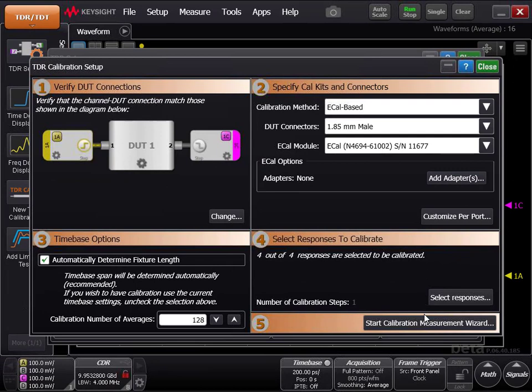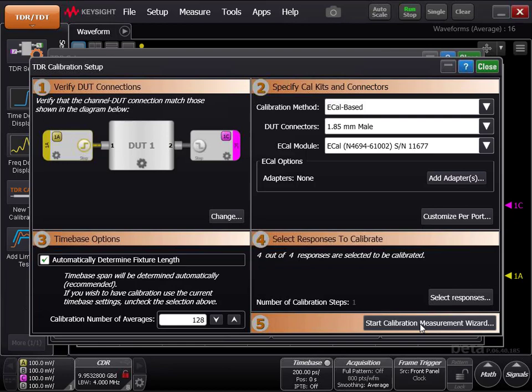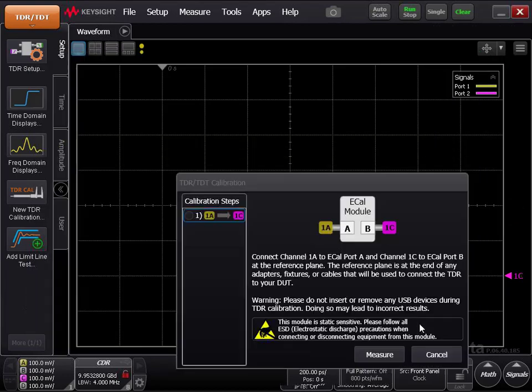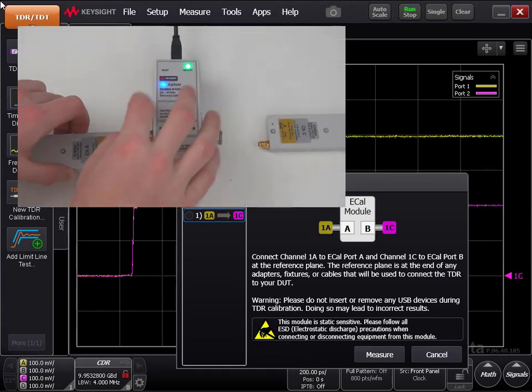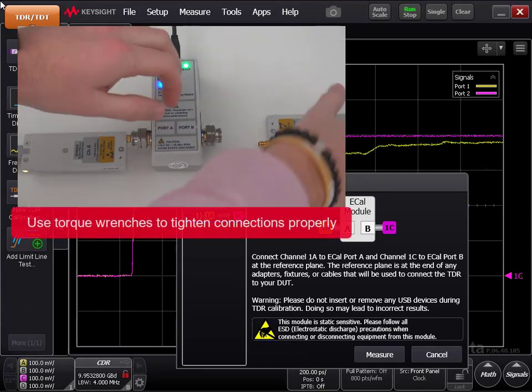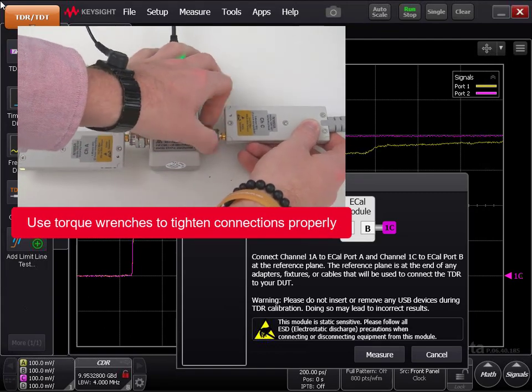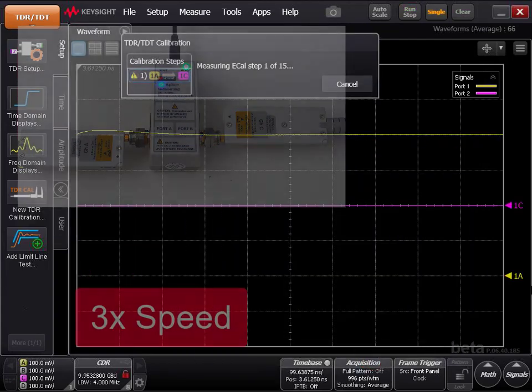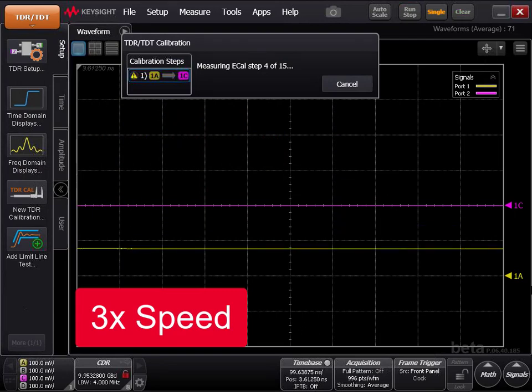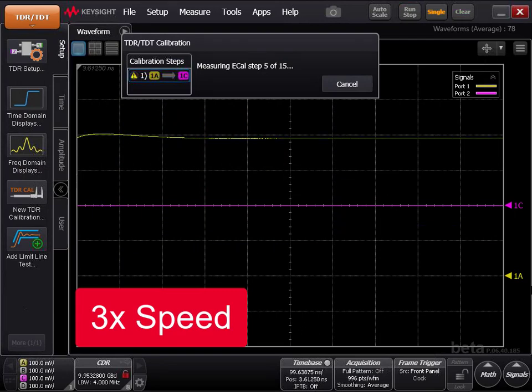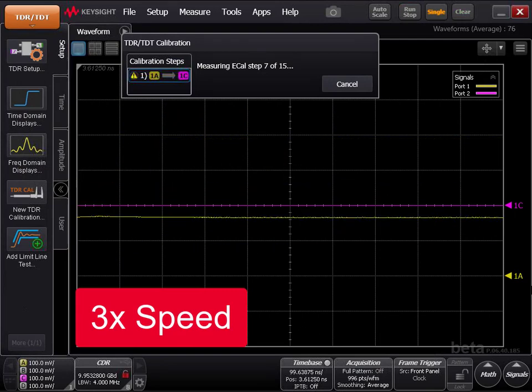Leave areas number 3 and 4 as they are. Next, click Start Calibration Measurement Wizard. Follow the instructions on the screen very carefully to perform the calibration. Please remember to follow all ESD precautions when connecting or disconnecting equipment from the TDR. The instructions will walk you through exactly what you need to do to perform an accurate measurement calibration.